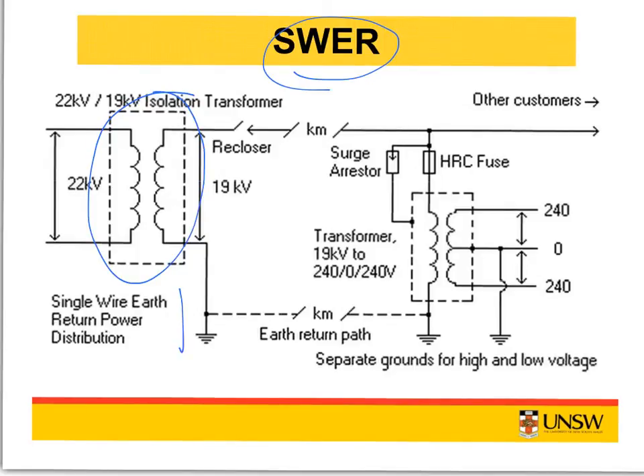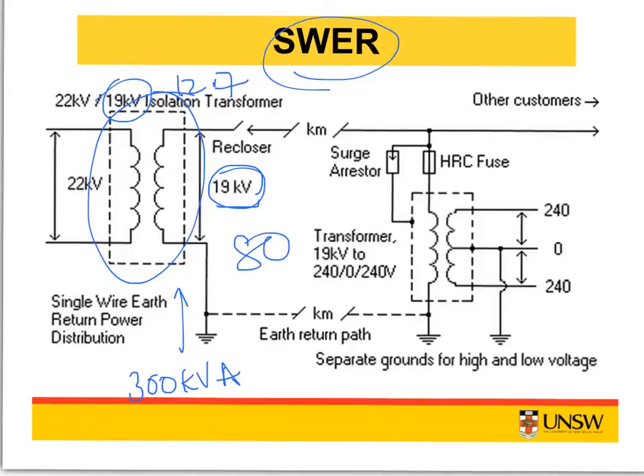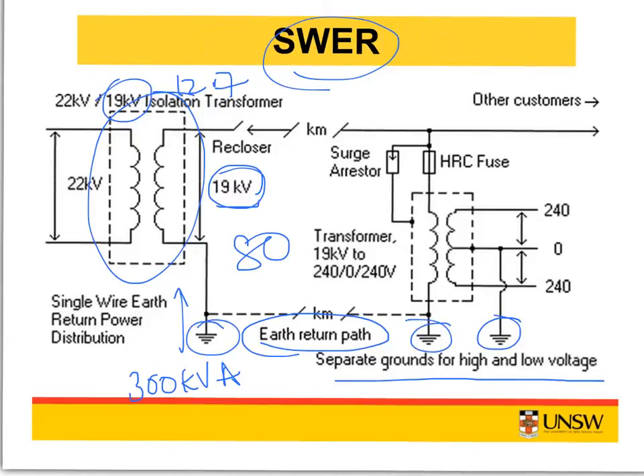The transformer has a capacity of usually up to 300 kVA. This transformer isolates the grid from earth and changes the grid voltage, typically 22 kV line to line or sometimes 19 kV line to line, to the SWER voltage, which is 19. From 22 it changes to 19 or sometimes 12.7 kV line to earth connection. So it's from line to line 22 kV, it changes to line to earth 19 here, and a large SWER line may feed up to 80 distribution transformers. So you can see here the earth return path is utilized. So separate grounds for high and low voltage sites are used. These groundings here are functional earthing, not for safety. These are functional. Safety earthing is separate. So there is only one line going there, but then the earth is taken as a return path.